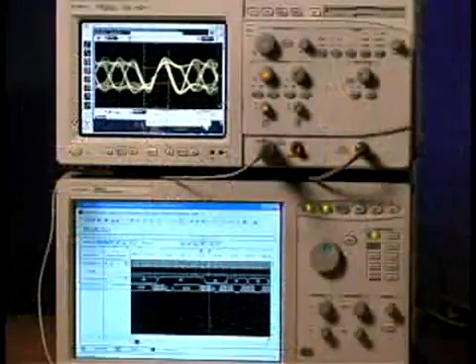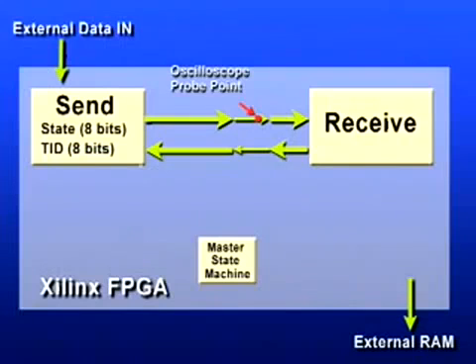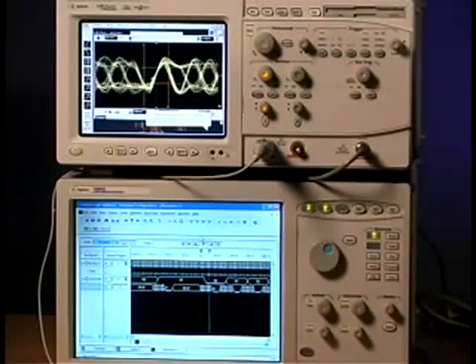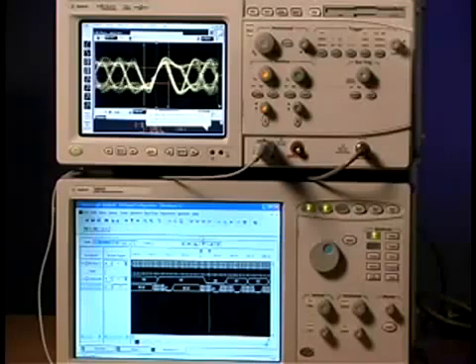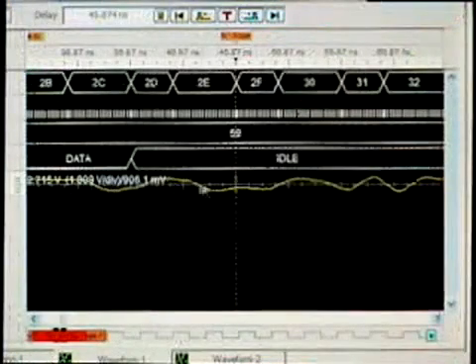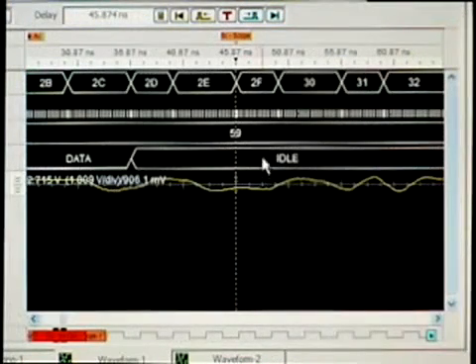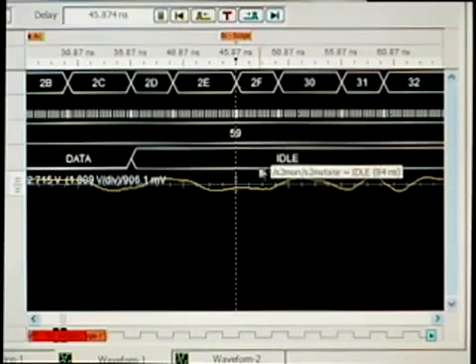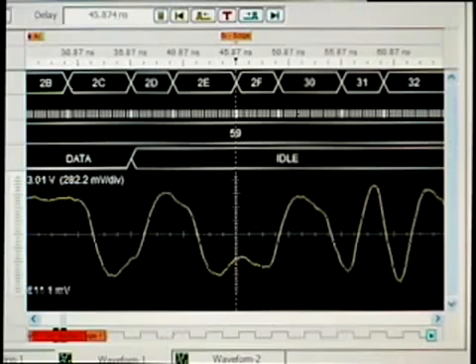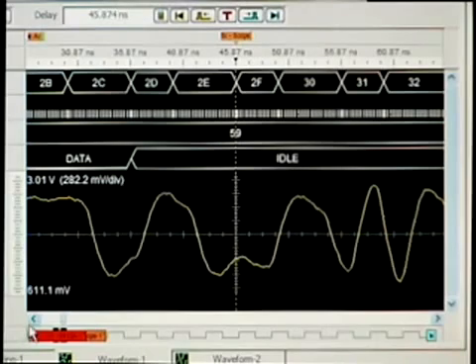Here I have an Agilent Infiniium oscilloscope that is looking at one of the serial channels that's part of this communication system. As you can see by looking at the waveform, there are a series of packets being displayed. I want to connect that Infiniium oscilloscope to my logic analyzer using my logic analyzer application software. If I hit the run button, you will now see that my scope waveforms are displayed along with my logic analysis waveforms, and they are actually time correlated. If I click and drag on this box, you can see that my data is auto scaled to fit the size of the row being displayed inside the logic analyzer screen.